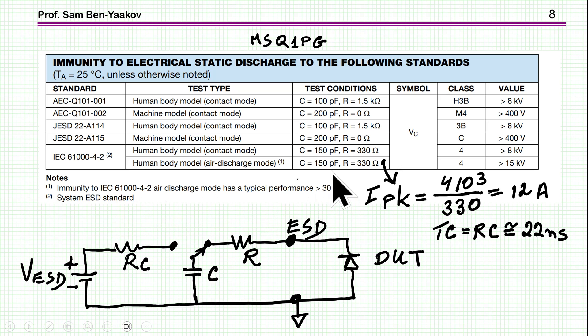And there are different values here for the testing for various classes. And what it is, in an approximation, this is not the correct network, what it is, that you have a setup like this, in which you charge the capacitor to a high voltage, and then you discharge the capacitor into the test unit through this resistor. So this is the capacitor, and this is this resistor.